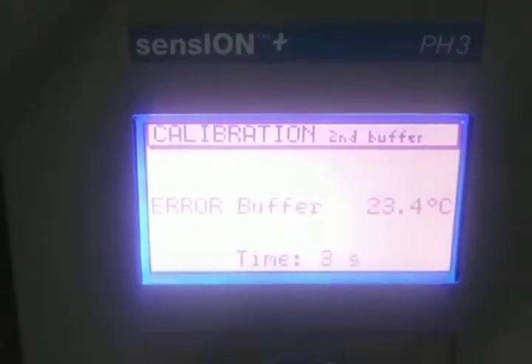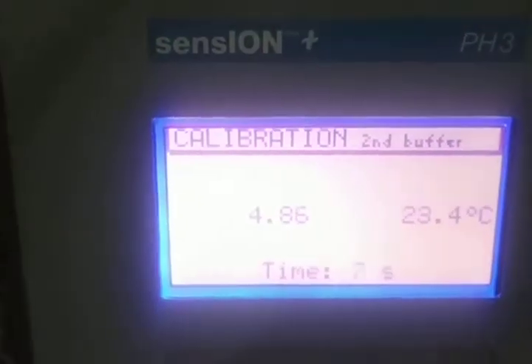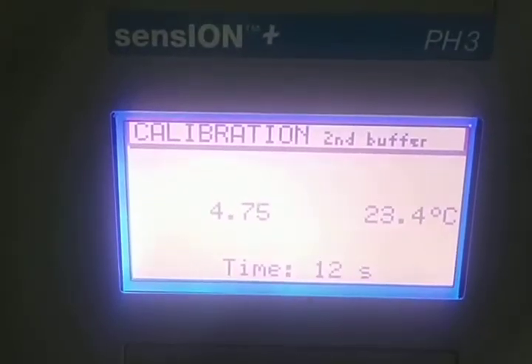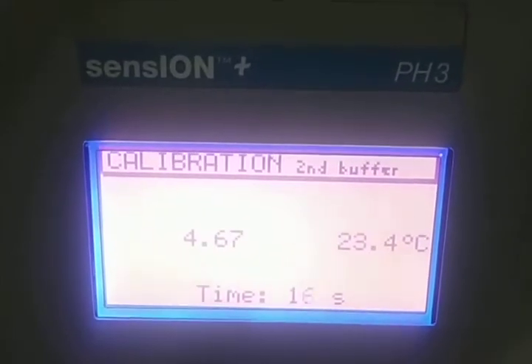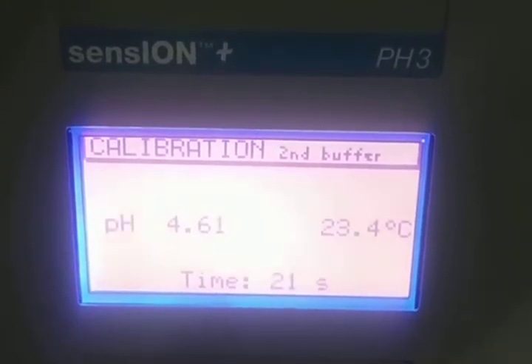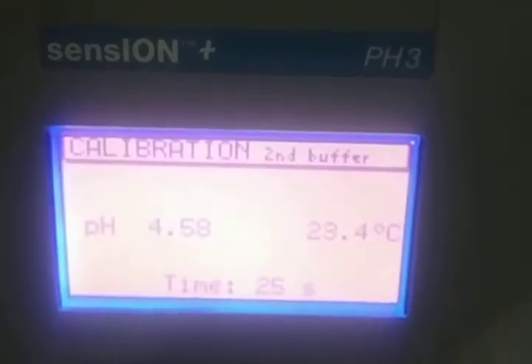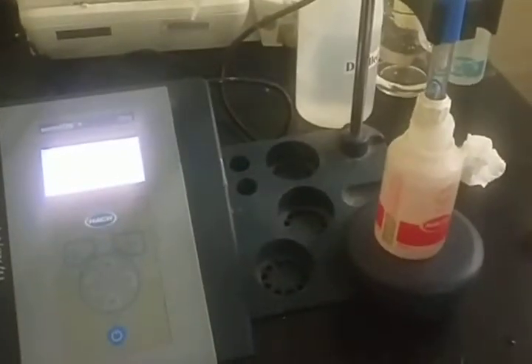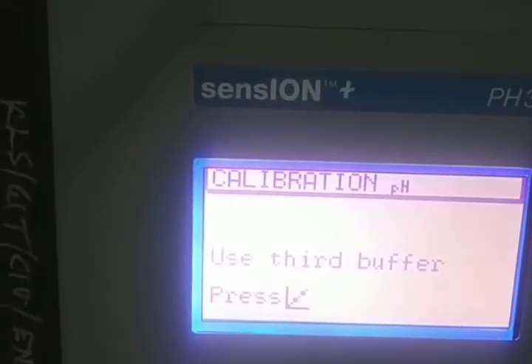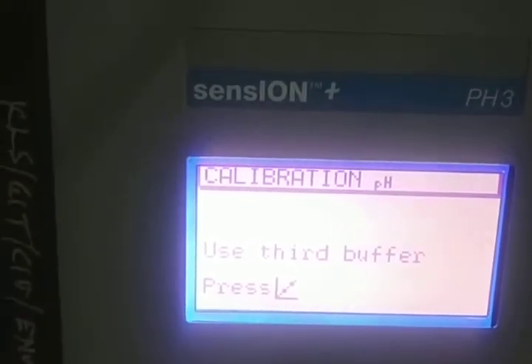Once it is pressed, the instrument is going to get calibrated for pH 4. So we have placed the buffer solution whose pH value is equal to 4. It is going to take some time for calibration. So this is how the setup is. This instrument has a stirrer which is inbuilt. Now the instrument is calibrated for the second buffer, that is pH 4.